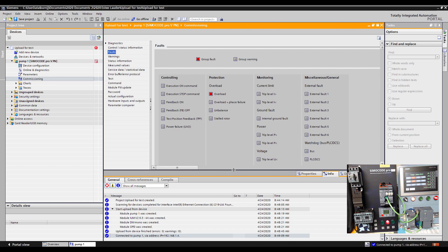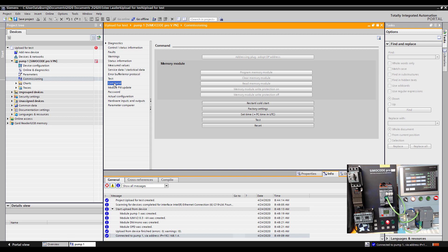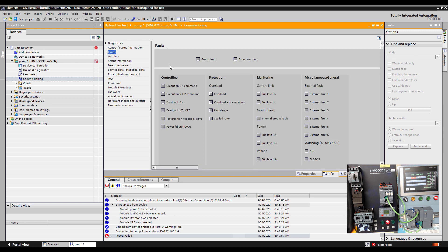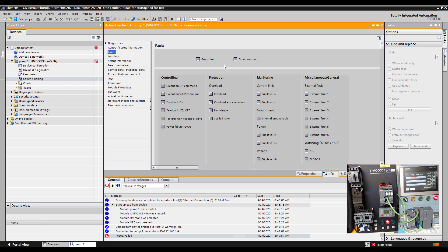Now while I'm here I can also come in and reset that function as well. So I come in here and click reset. And if I come back to my fault conditions you can see the fault has also been cleared. So from the software I can diagnose what the problem was and I can also externally reset it. If something hasn't been configured, say in the PLC program to reset it, I can reset it directly from the portal software as well.